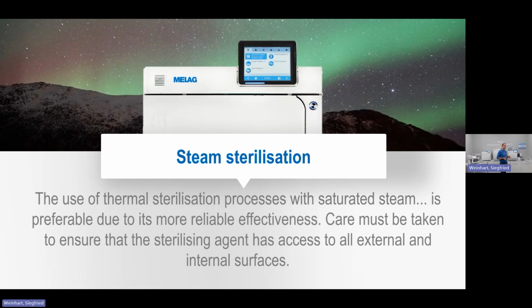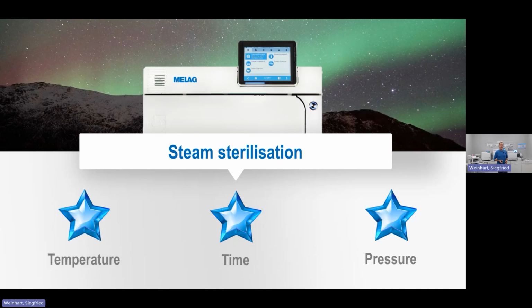There are three primary things we look at when we look at steam sterilisation: temperature, time, and pressure. So an instrument going into a steam steriliser at 134 degrees with a pressure of around 3 bar, which is typically what a vacuum autoclave will look at, sterilising for at least 5 minutes, is going to have at least a 6 logarithmic reduction in the amount of pathogens on that instrument. To put that into context, if there were 1 million pathogenic organisms on an instrument when it went into the steriliser, under those three conditions you'd be looking at no more than 1 pathogenic organism on the instrument when it comes out the other side.